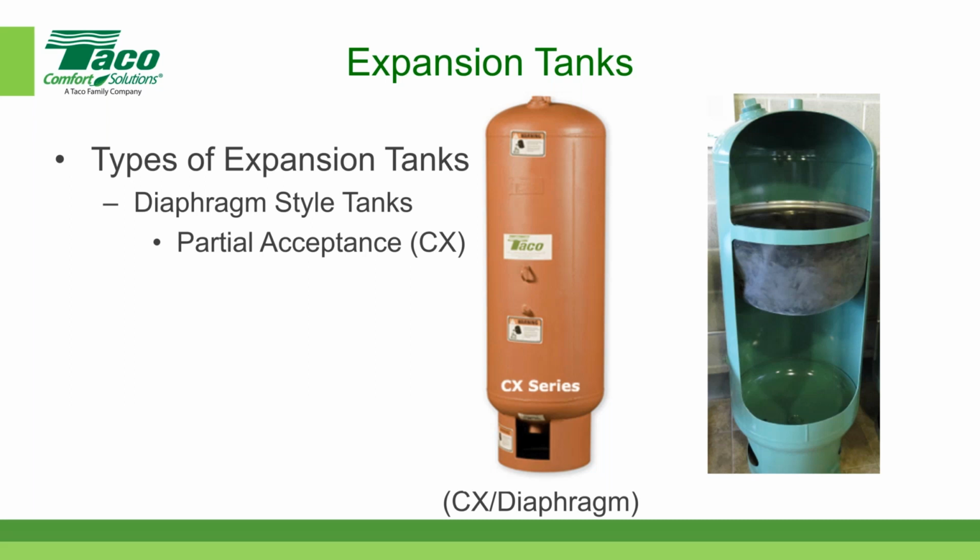The diaphragm is connected to the inside of the steel tank along its circumference. The main difference between this style and the previous styles is that the diaphragm cannot be replaced. If it should fail for any reason, then the tank has to be disposed of. It cannot be repaired. The diaphragm cannot be replaced.